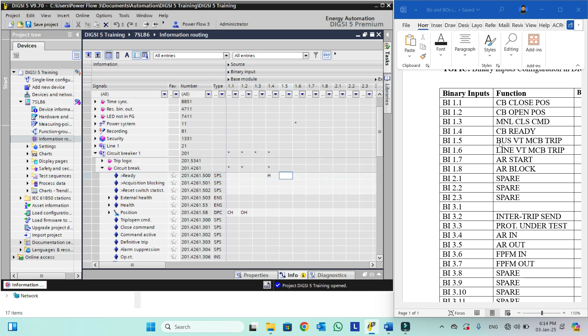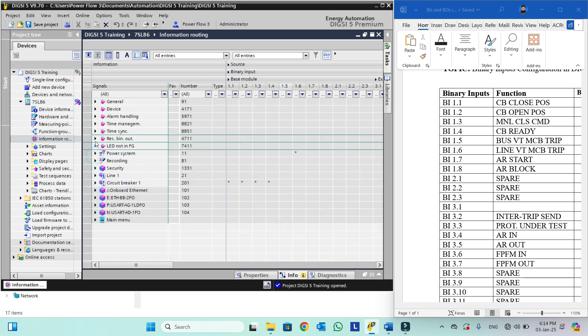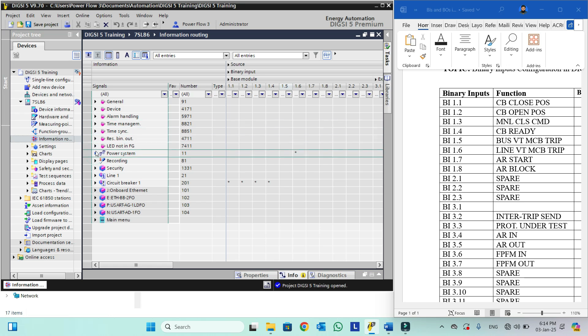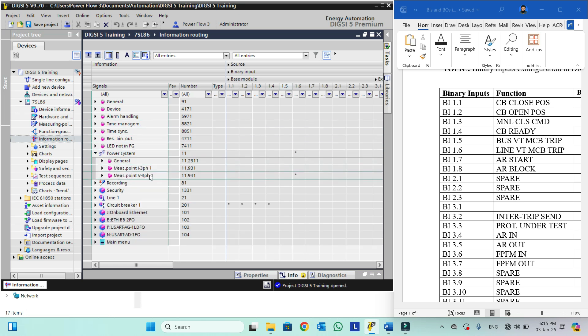Now the fifth one is bus VT MCB trip. We will go into power system. Here we have V3 phase, but I have not added this bus VT, so we cannot configure the bus VT. The V3 phase is for line VT. For this we actually need the bus voltage function group, which is not available in this configuration.